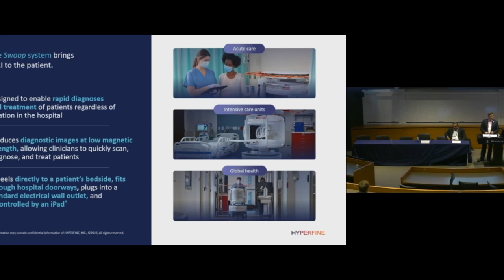Just curiously, how does it work with the superconductor coolant? How often do you have to refill it? We don't have that, it's a permanent magnet, there's no superconductor. Oh, yeah, it's only 0.06 Tesla or something. It's a permanent magnet. And is there any concern with pacemakers and stuff, or not really? It's too light. As long as the pacemaker is cleared for anything below our field strength, no issues. And as long as it's outside the 5 Gauss line of the scanner, which is really 2.5 feet from the center, no issues with that.